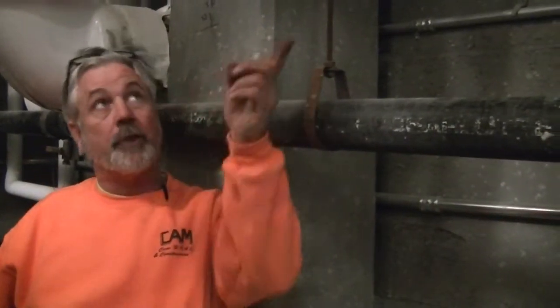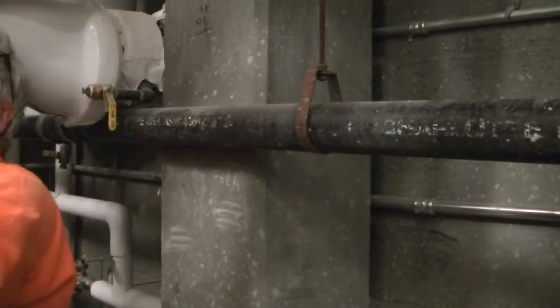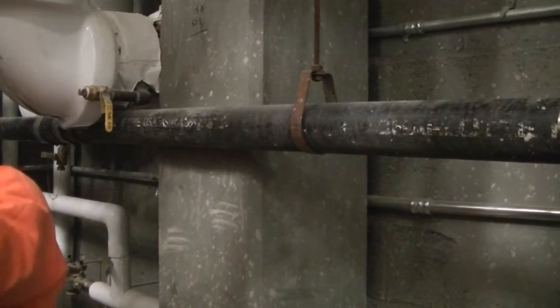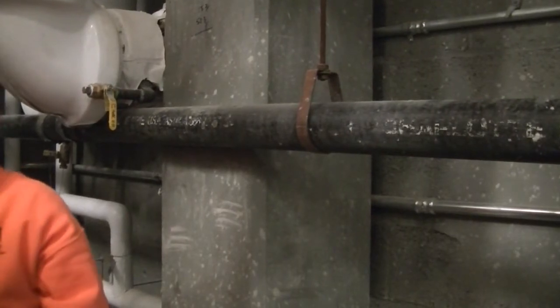Is there anything they need to do with the strainer? Clean that out? Yeah, once the job's done, we're going to have chemicals in here, rust inhibitors, things like that. You have mud strainers here. Plus you have a spiral vent here to take air out of the system. We put this hose on here just to keep the place looking clean. The project's done, this is going to disappear. The mud strainers, you can hook a garden hose up to them, blow them down once a year. Once the chemical's in the system, you shouldn't see any buildup in here.